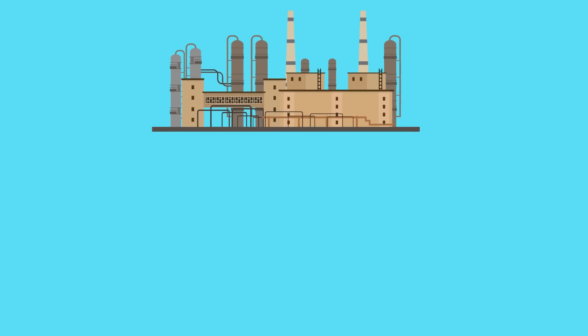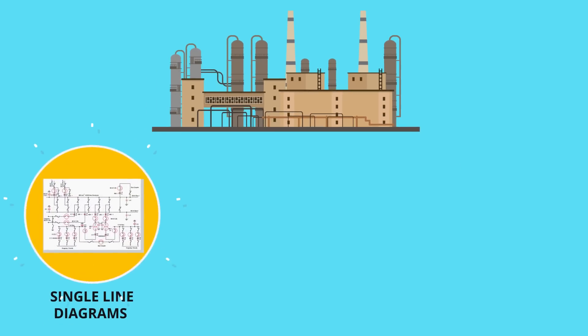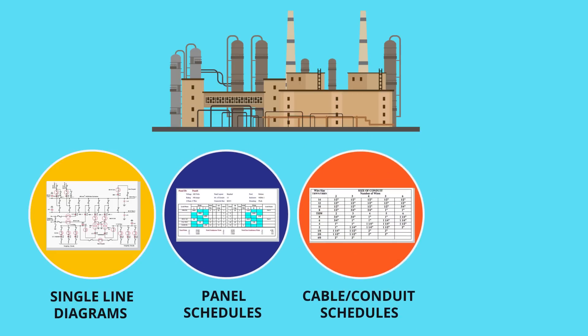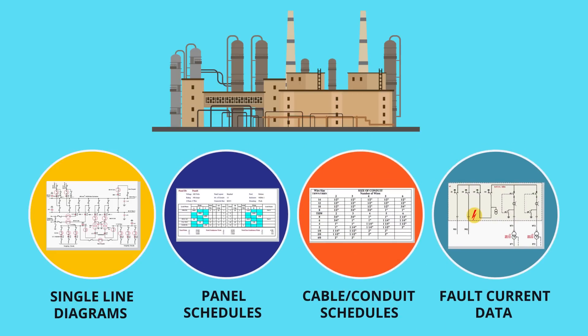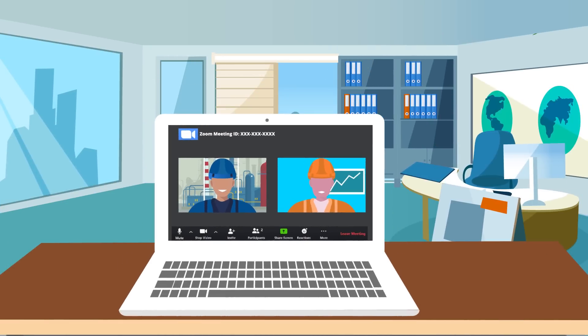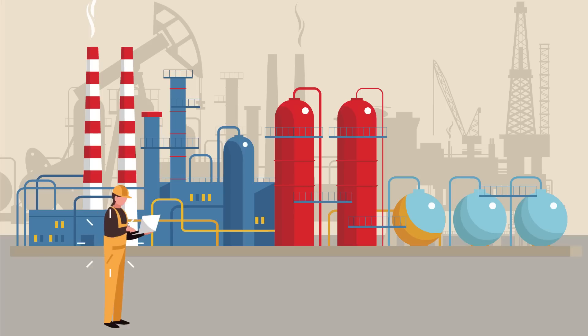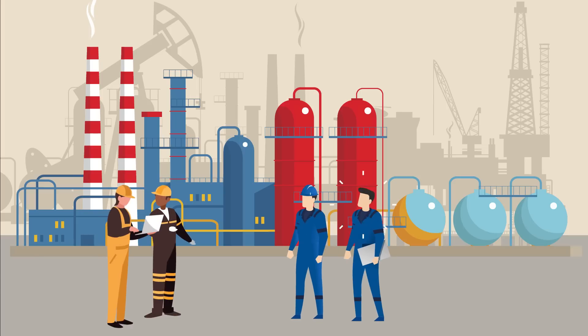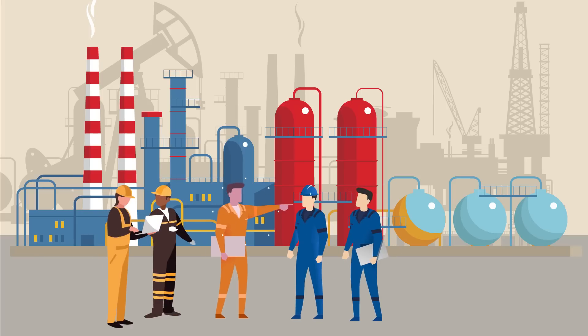First, collect existing documentation on the system, including single-line diagrams, panel schedules, cable conduit schedules, and utility-available fault current data. Following this, perform field verification with a qualified and knowledgeable engineer or technician. Ensure the person verifying equipment is experienced in performing this task to minimize missing data.